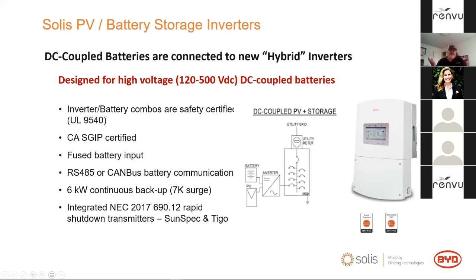That's the kind of versatility you get with a hybrid like this. Now that involves, like Devin said, some more commissioning process than you'd have with just a simple grid tie inverter. With a hybrid inverter, the inverter self-configures for grid tie, anti-islanding, and all that functionality. This is also a Rule 21 capable unit that can do volt-var, and does ramping of both voltage and hertz rate, that sort of thing.